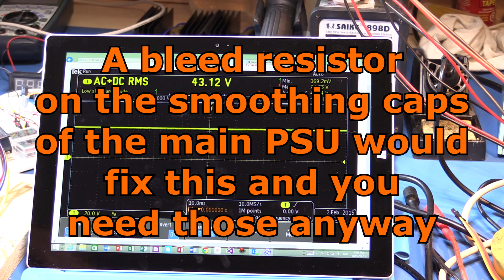But if you don't know that's happening, you could get thrown and wonder what the heck's going on with your circuit. So yes, voltage doublers work and everything else, but you do need to be wary of the fact that under no-load circumstances, if you don't have any internal load for your control system, they can drift the voltage up slowly on your power supply.